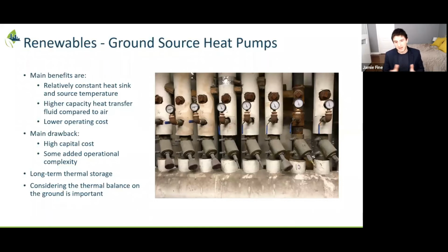We know of many schools that, back in the early 90s, there was kind of a move to start putting ground source heat pump systems in, and it really turned people off because the systems just stopped working. They promised everything, and then they just wouldn't work anymore. They couldn't meet the heating demands. Those systems weren't balanced. They were drawing a lot of heat out during the winter time and not putting much in during the summertime. And as I said before, if you're doing this, what ends up happening is that temperature of 10 degrees that you're getting out of the ground just starts going down year over year. And you need to make sure that these systems are balanced.